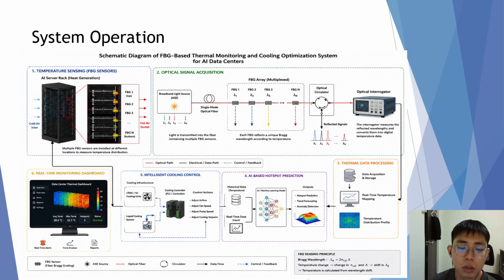First we have the FBG sensor. It is the primary sensing element used to measure the temperature inside the AI server rack. Each FBG sensor contains a periodic refractive index grating that reflects a specific wavelength of light. When the surrounding temperature changes, the reflected wavelength shifts proportionally, allowing accurate temperature measurement at each sensing location.